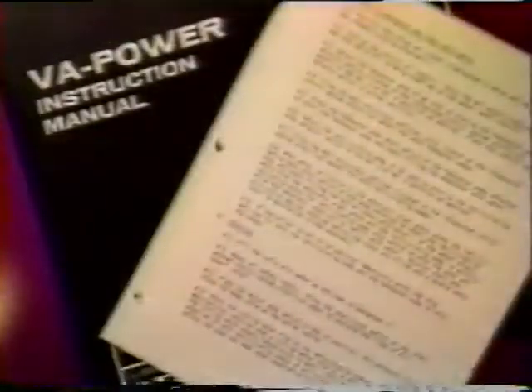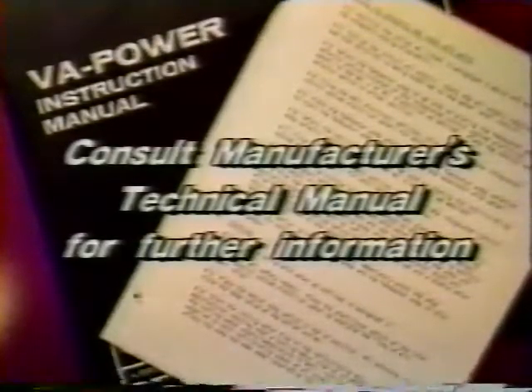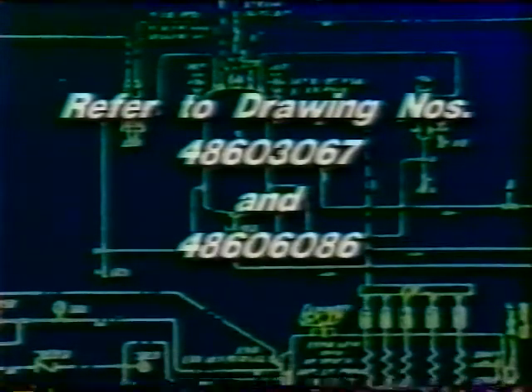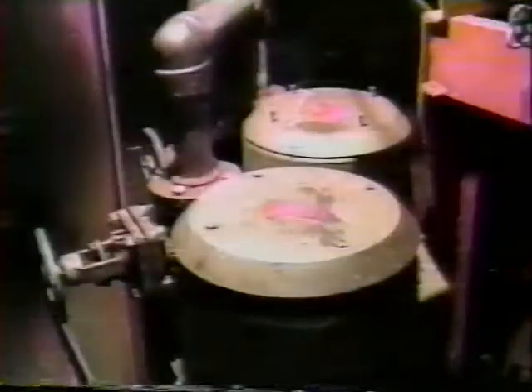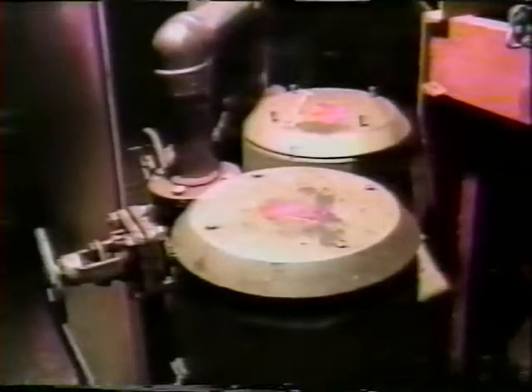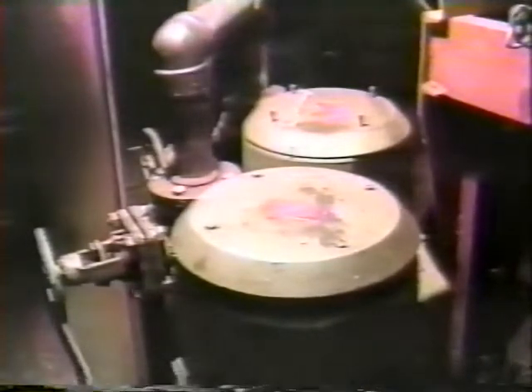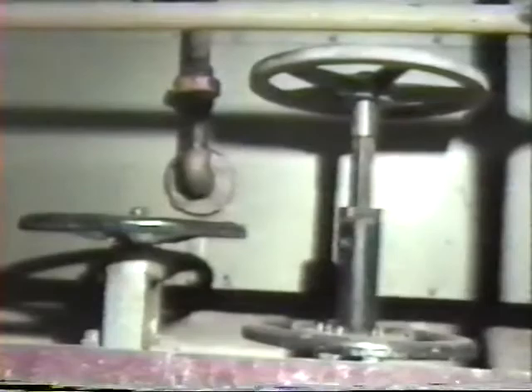To operate the boiler, all valves must first be arranged properly. Consult the operating instructions contained within the manufacturer's tech manual. Refer to schematic piping diagrams of VA-POWER drawing number 4860-3067 and drawing number 4860-6086. Remember that the exhaust gas boiler has feed water supply pumps common to the separately fired water tube boiler. Once all valves are positioned correctly, the control air supply is activated. The feed water pump and recirc pumps are brought online as detailed in section 3.0.